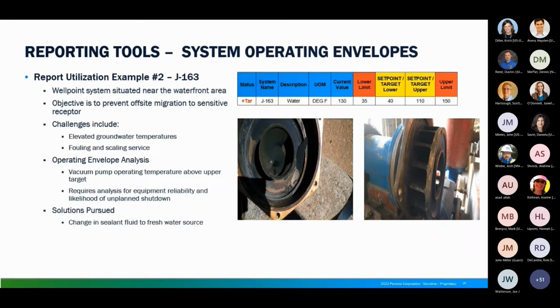It's about 20 degrees above our upper target. We know that as that vacuum pump temperature gets hotter, it increases the likelihood that we have an unplanned outage due to the vacuum pump seizing. So that helped us to better forecast when we might see an unplanned outage, since we typically know that as we start to see those recorded temperatures increasing, they usually increase fairly exponentially. So we're able to use this operating envelope feedback to identify that ahead of having those unplanned outages.